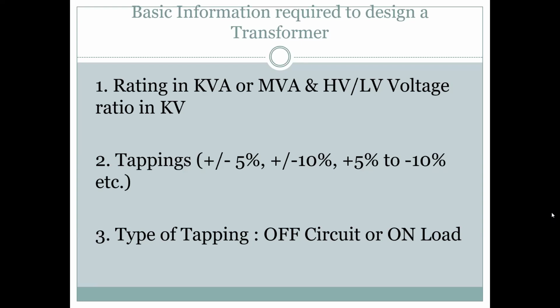There should not be any disturbance. That is why there is the compensating winding. When voltage goes up, we take turns out of the circuit, and when voltage goes down, we add turns to the circuit. This can be done manually or automatically. This is called off-circuit tappings and on-load tappings. During transformer running, there is a mechanism called the on-load tap changer. It changes the taps depending on the voltage fluctuation, in steps of 1.25% or 5%, whatever setting is required. And off-circuit tapping: here is a misnomer. Many learned engineers in many industries confuse off-circuit and off-load.